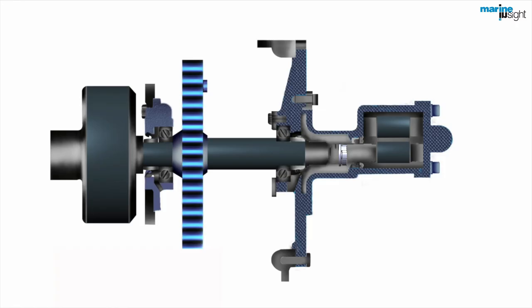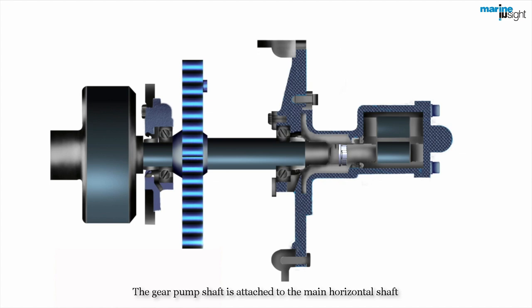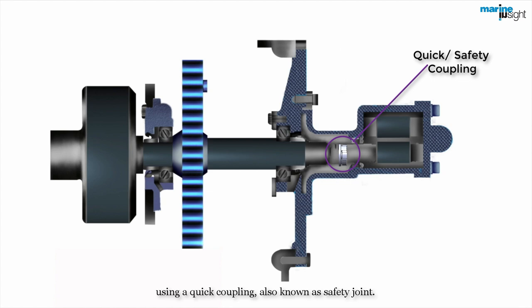The gear pump shaft is attached to the main horizontal shaft using a quick coupling, also known as safety joint. This coupling will break in the event of a stuck gear pump, thus avoiding overloading in the main shaft and the motor, preventing significant damage.